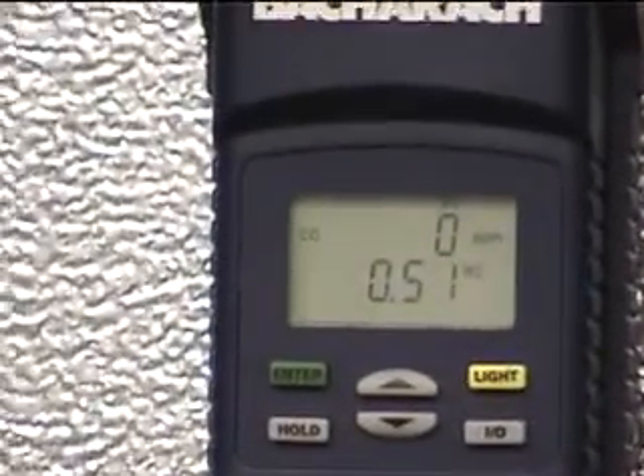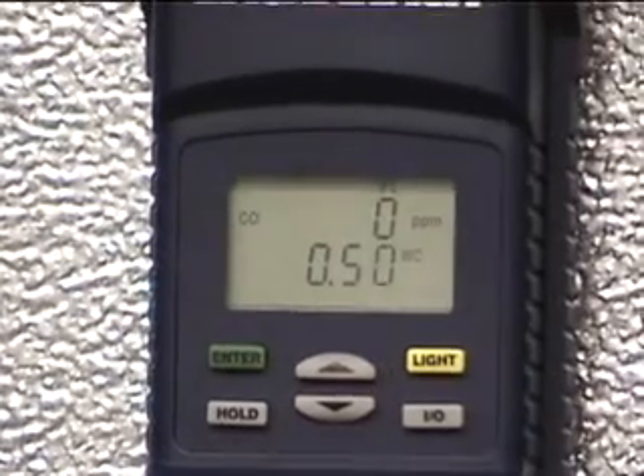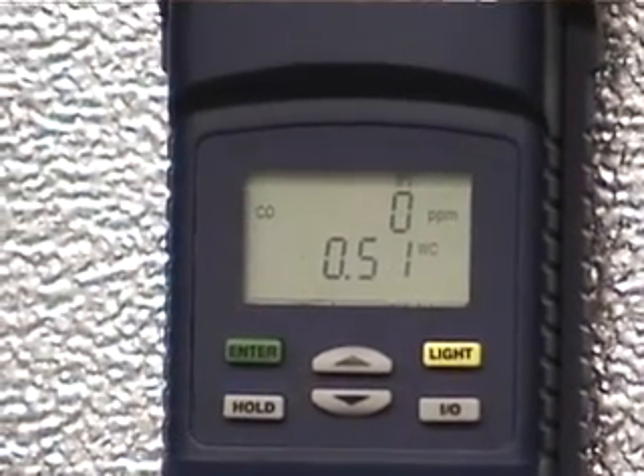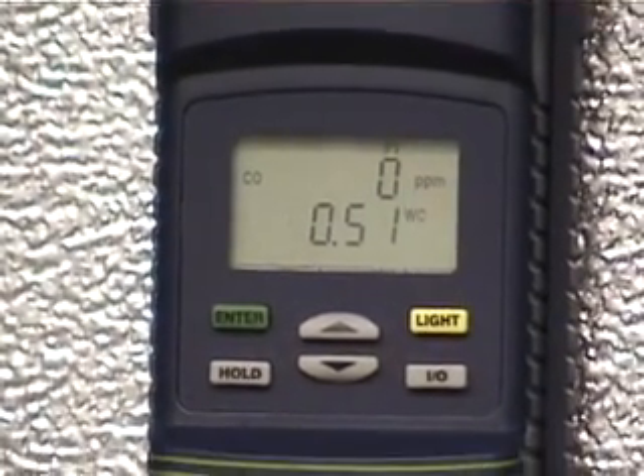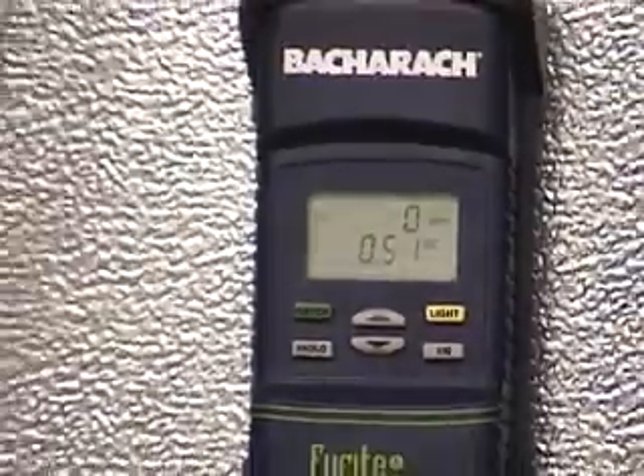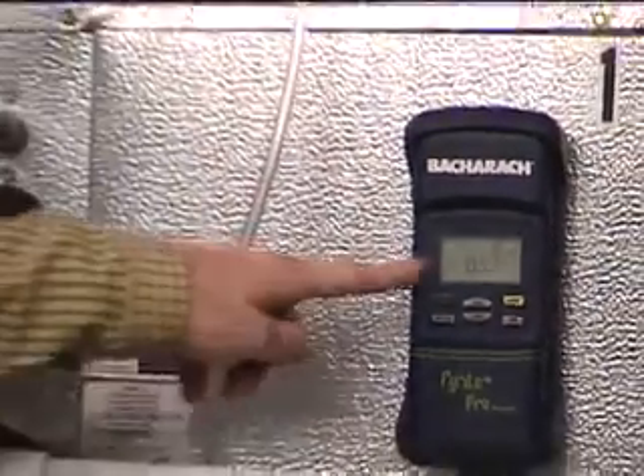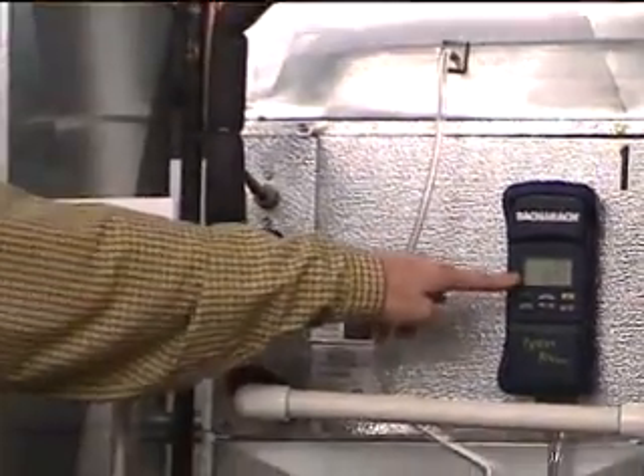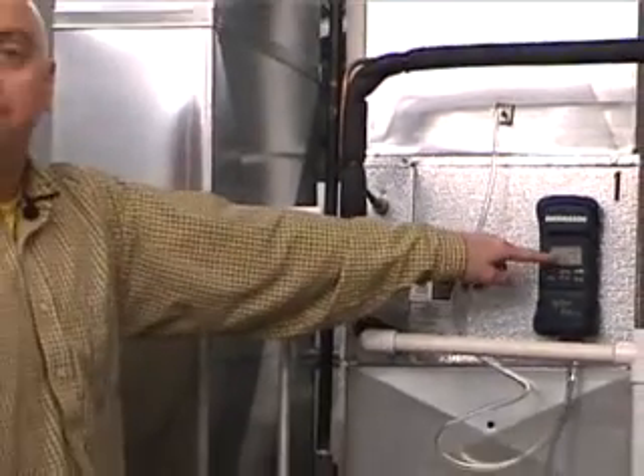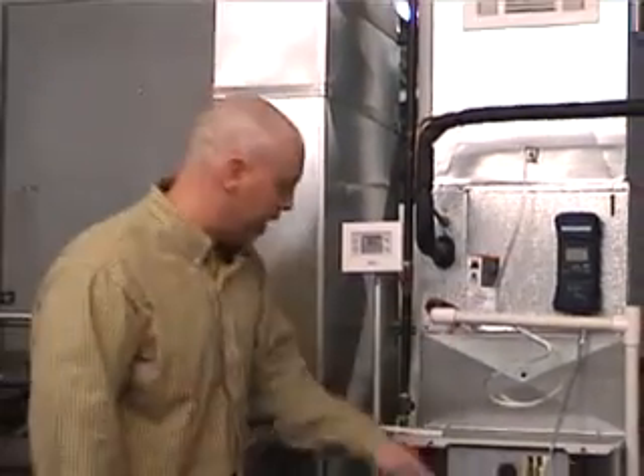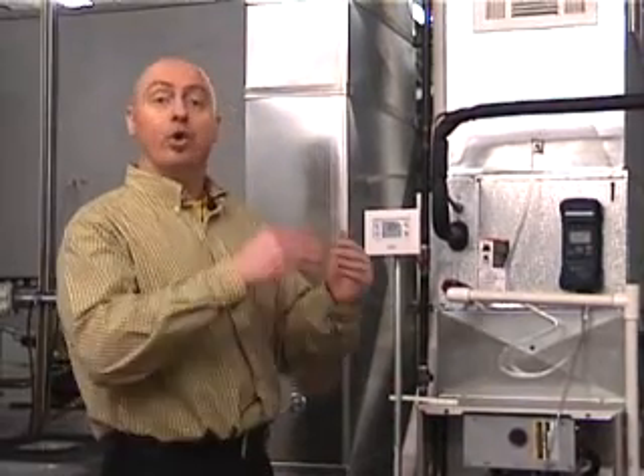Okay. I shut down some of the return air. So now we have the technician came out. He accessed in the wrong testing locations. He is on the plenum area, he is in the return air drop, and then he reads his meter. His meter says 0.50 inches of water column, which looks like a pretty good number. He comes over here to the name tag of the unit and says, that is normal. I am right at the maximum level, so I have a good duct system.